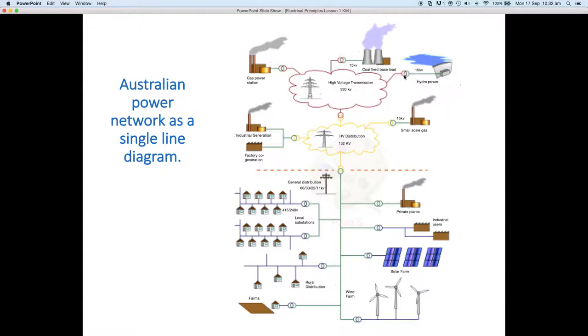A transformer takes 15,000 volts up to 330 kV, and that's what we call high voltage transmission. That's for transmitting over hundreds and hundreds, maybe even well over a thousand kilometers from where the power is generated. We then come into big substations. You can see here, normally very large substation yards with big aluminum conductors and switches and circuit breakers and transformers.